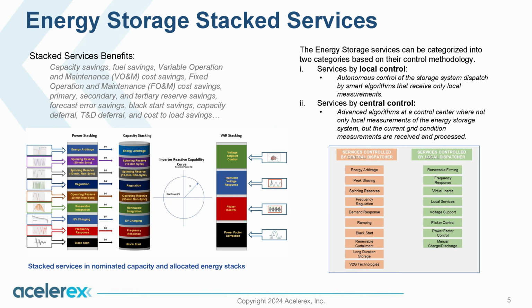So where storage really reveals itself as very valuable is 4-quadrant stack services. What are 4-quadrant stack services? It's the power, the stack power services, and stacking up the capacity of the storage through the inverter capability curve, stacking up reactive services like voltage set point control, transient voltage response, flicker control, power factor control. And then some of the power strategies: energy arbitrage, regulation reserve, renewable integration, charging, frequency fast response, and black start grid-forming inverters.